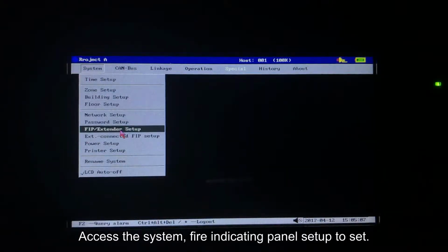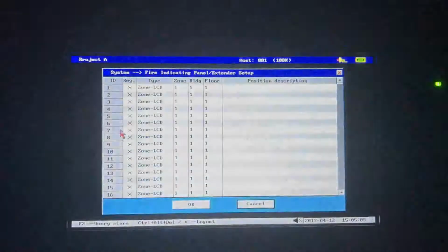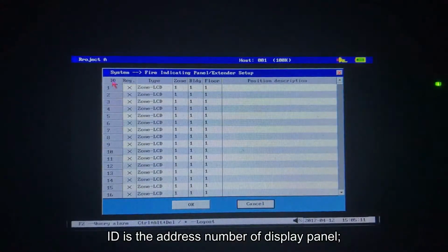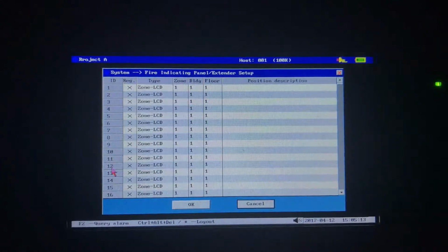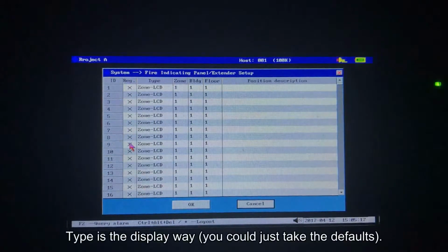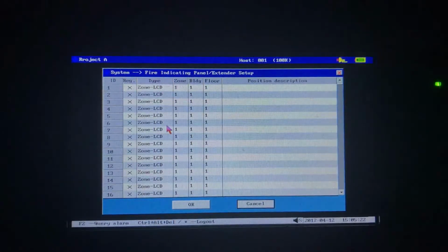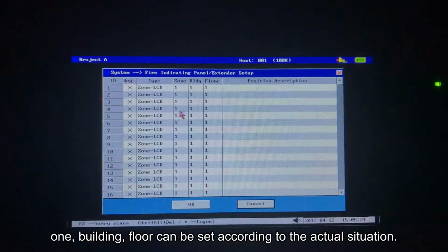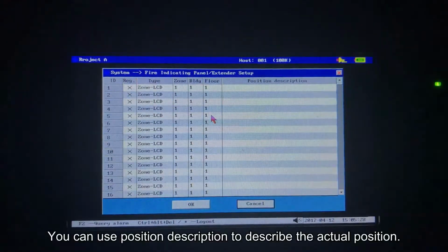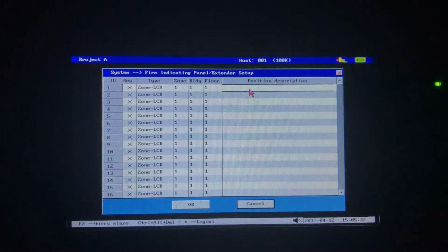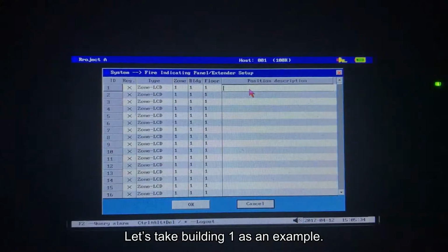Access the system. Fire indicating panel setup to set. ID is the address number of the display panel. REG is the registration. Type is the display way. You could just take the defaults. Zone, building, floor can be set according to the actual situation. You can use position description to describe the actual position. Let's take building 1 as an example.